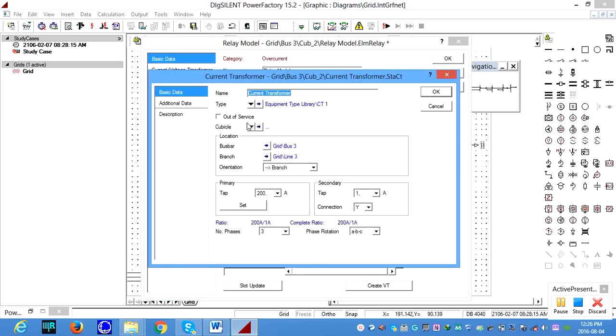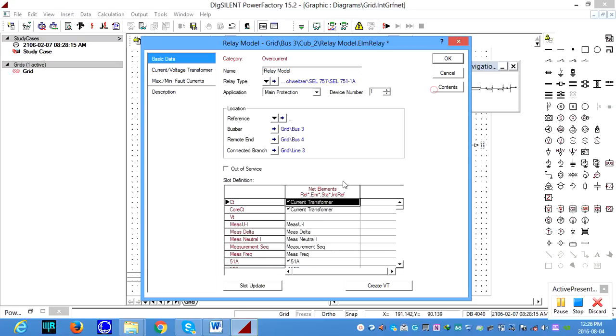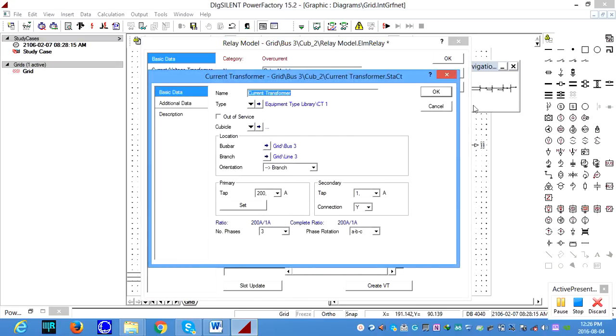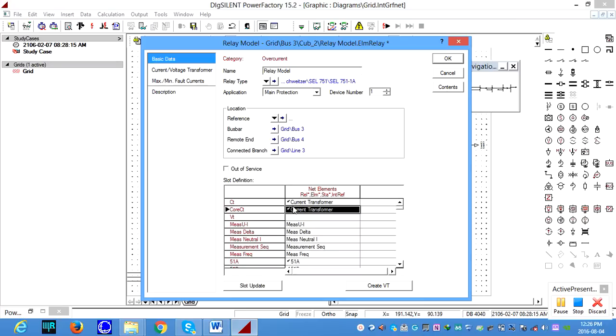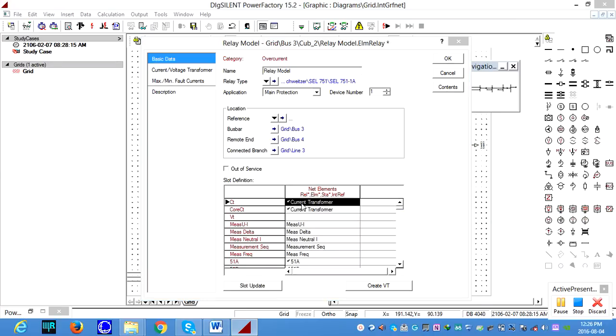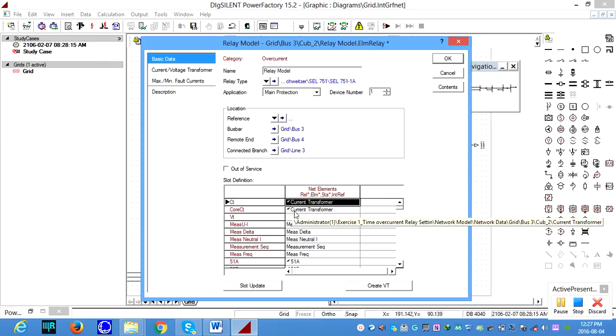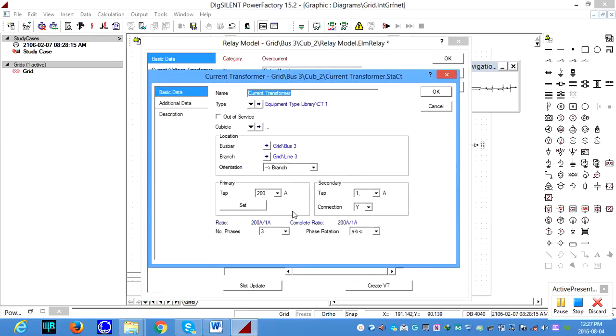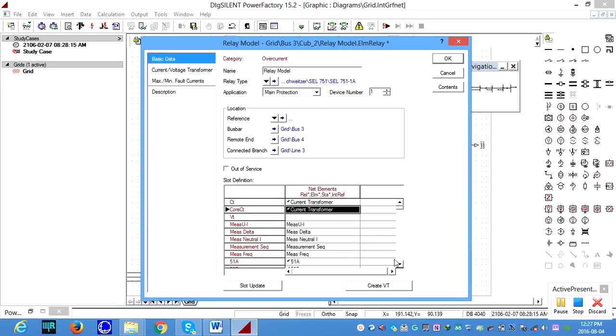If you look here, the current transformer already 200:1 amps is in the library. I think there are two current transformers. One CT is used to measure the currents on the specific location of the network, and the other is a core CT that is also used to measure the currents on the specific equipment where you loaded. In this case, you don't worry about the VT because it's purely an overcurrent element. You not bother about that.